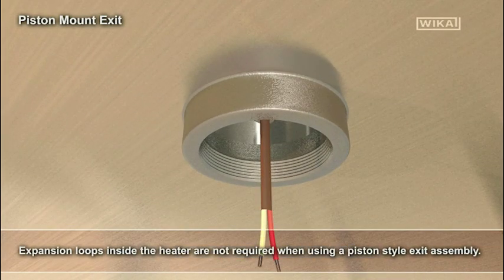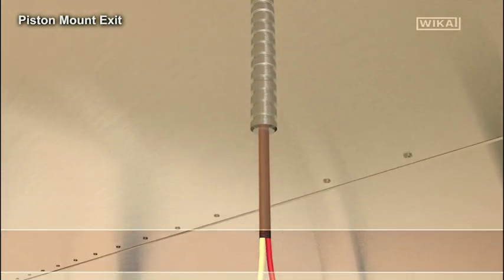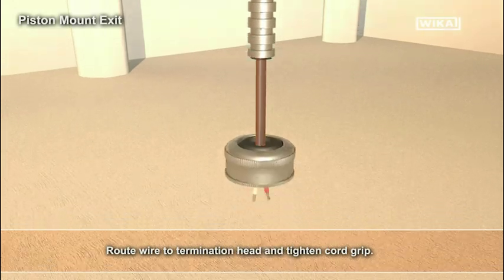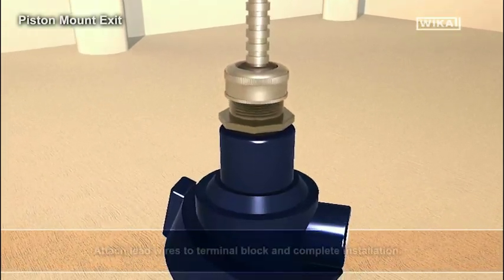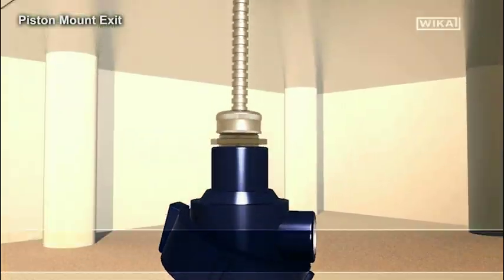Expansion loops are not required when using a piston style exit assembly. Pack the exit orifice with Kaowool to keep outside connections cool. Route wire to termination head and tighten cord grip. Attach lead wires to terminal block and complete installation.